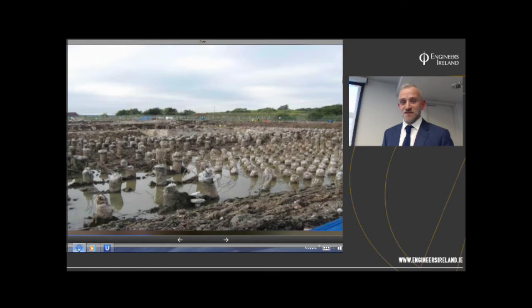We couldn't remove all these piles because of their depth, so it was decided to cut them all down 4 meters below ground level, and then do precise surveying of the exact location of each pile, their exact diameter and verticality, because not all the piles are vertical, some were at angles. With that data gathered, we gave it to our EPC contractors so that when they designed their piling solution for the new power plant, they were able to thread their piles into the gaps between the old ones.